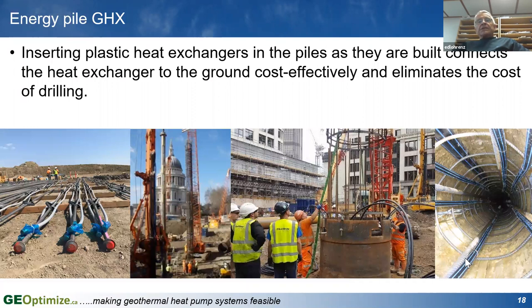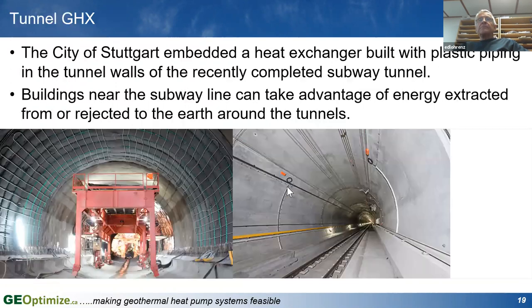I mentioned installing pipes in piles. If you've got a deep enough pile, you can install a lot of pipe in there fairly cost effectively. You don't have to worry about the drilling cost. All you're doing is attaching the pipe to the steel rebar that's already installed in the system. In other places, people have embedded pipes in the walls of tunnels and subways, and this is happening in Europe, in Stuttgart and in a couple of other places. That can be a very cost-effective way of getting a lot of pipe to touch a lot of dirt.